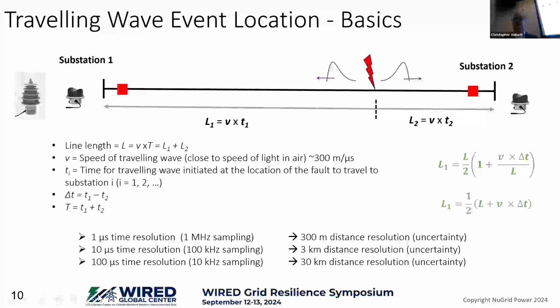Not very helpful. But when you get to microsecond resolution, because in a microsecond the wave travels about 300 meters—speed of light, people like to say 3 times 10 to the power 8 meters per second, I like to call it 300 meters per microsecond in a more practical way, or 1,000 feet per microsecond—with that resolution you can have that accuracy in fault location, and it becomes a lot more practical and useful.